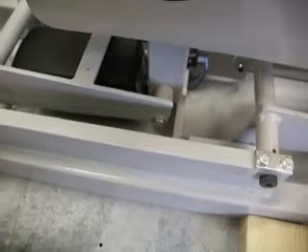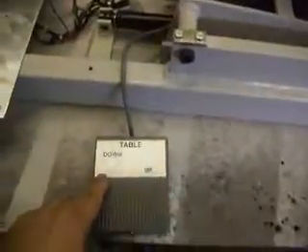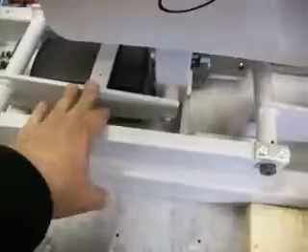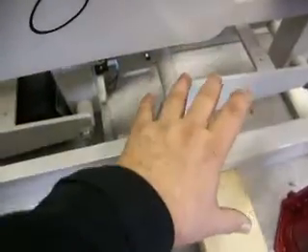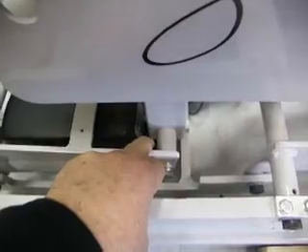While the table is in a blocked condition, if someone should apply power to the table and press the down button, this linear actuator — which is capable of lifting over 1,500 pounds — will find itself in a position where the table is mechanically blocked while electrically being commanded to lift the table. The consequence is that the linear actuator mount point can be broken or damaged.